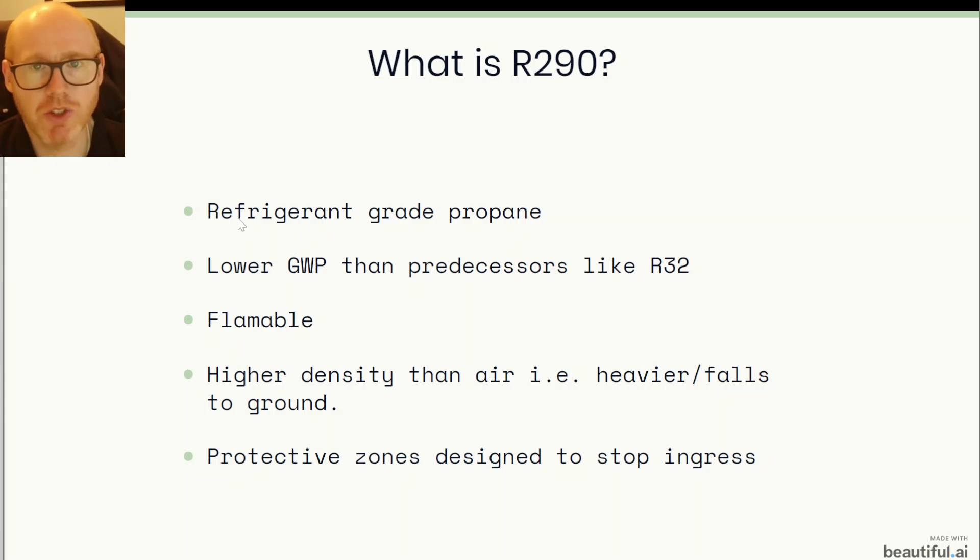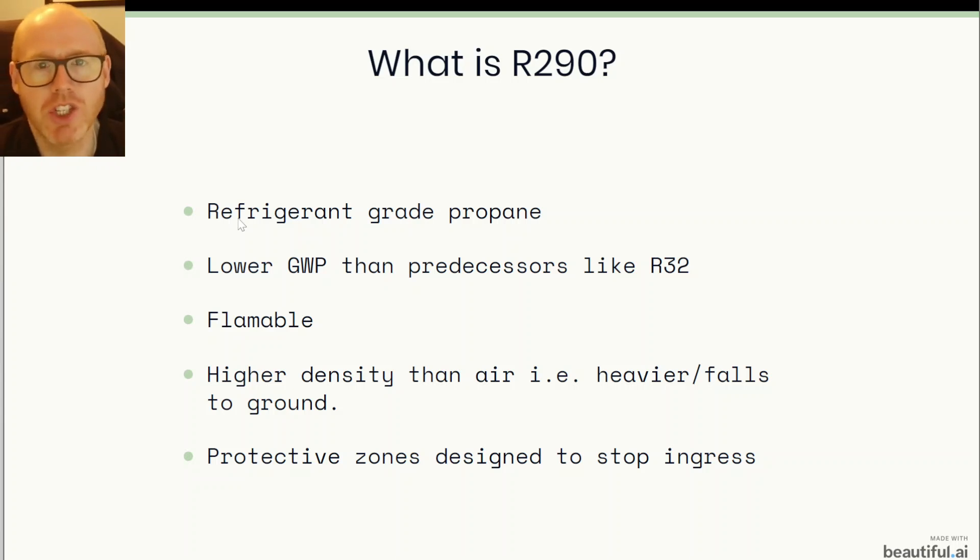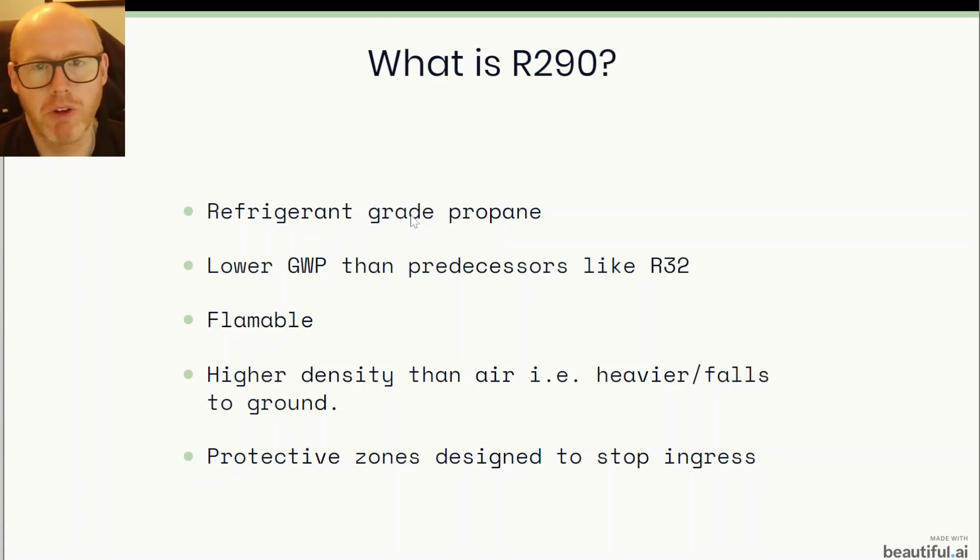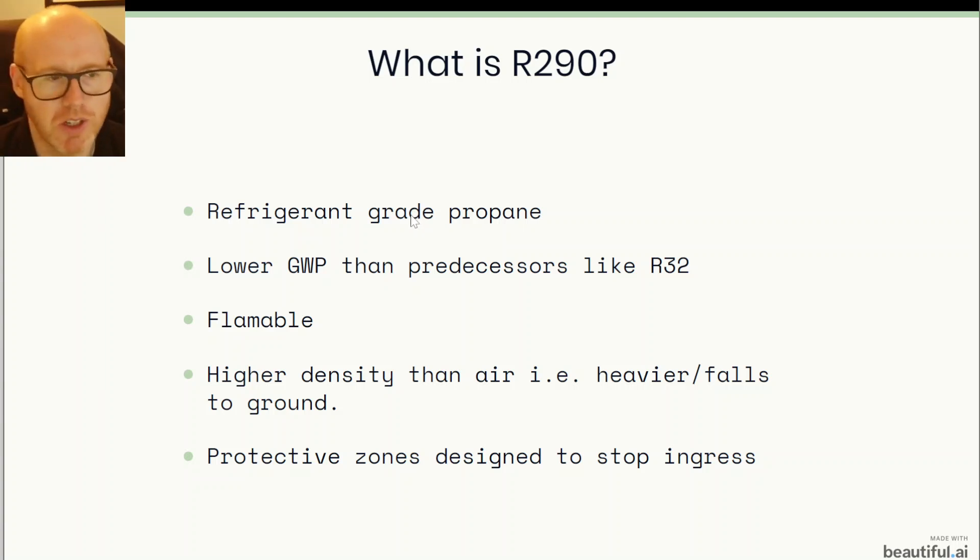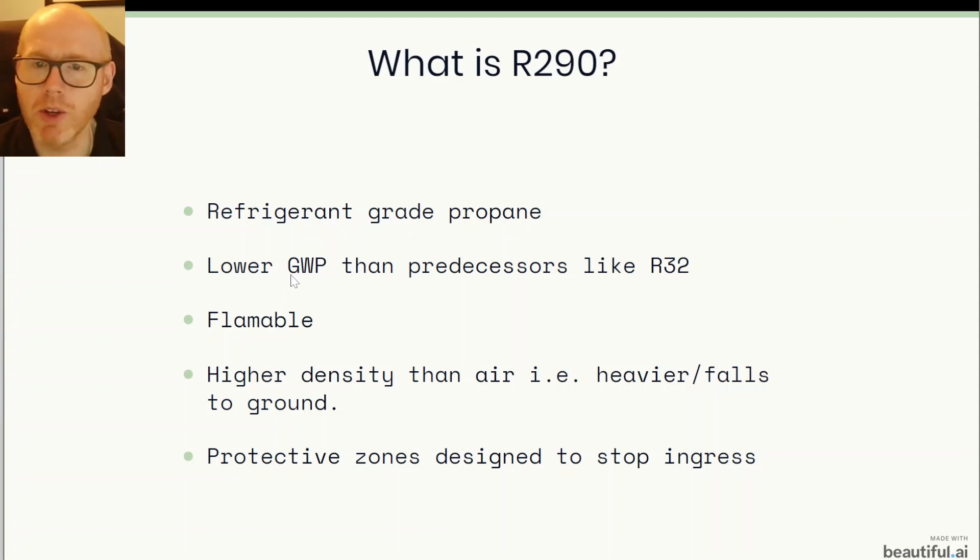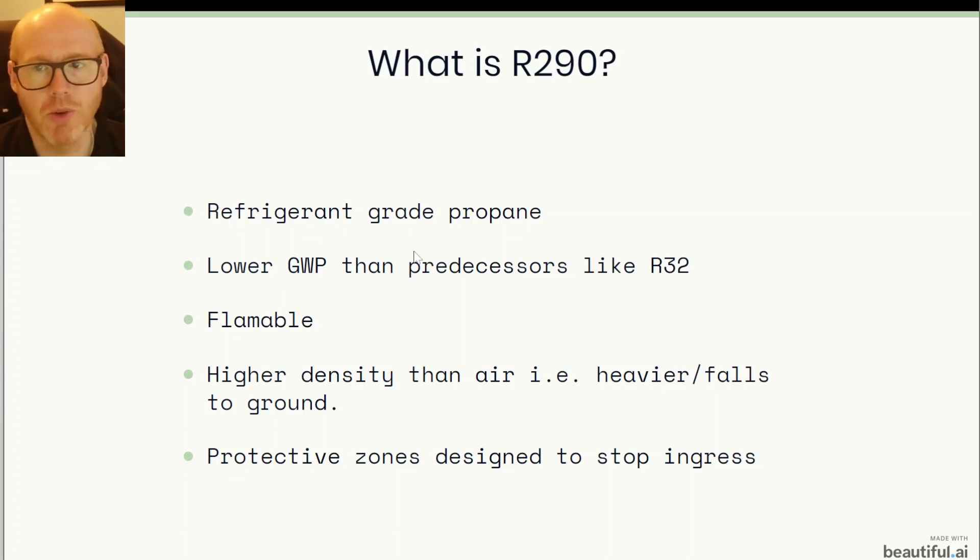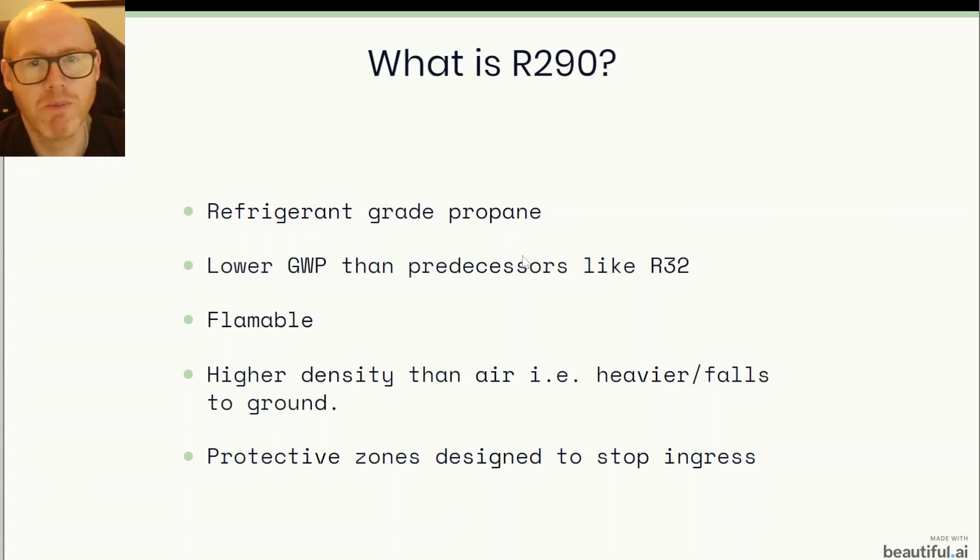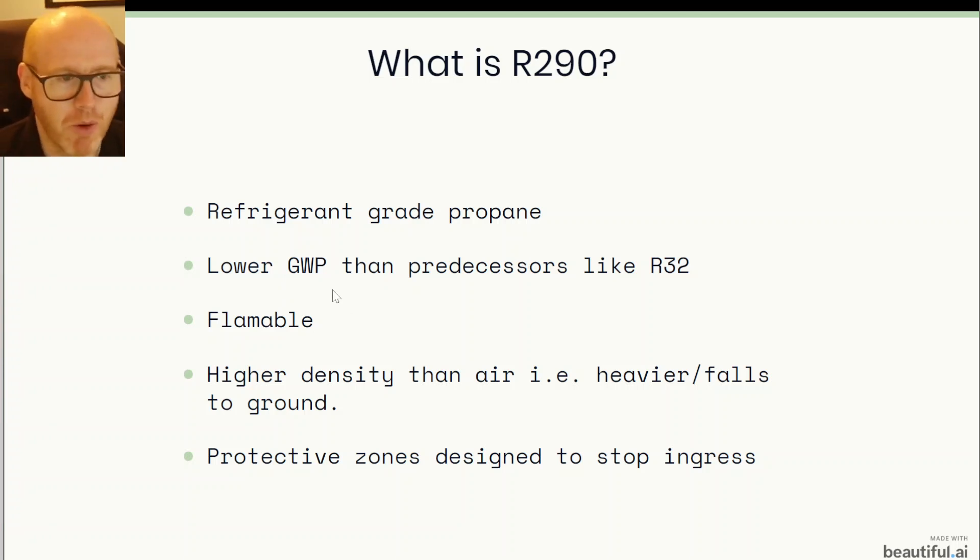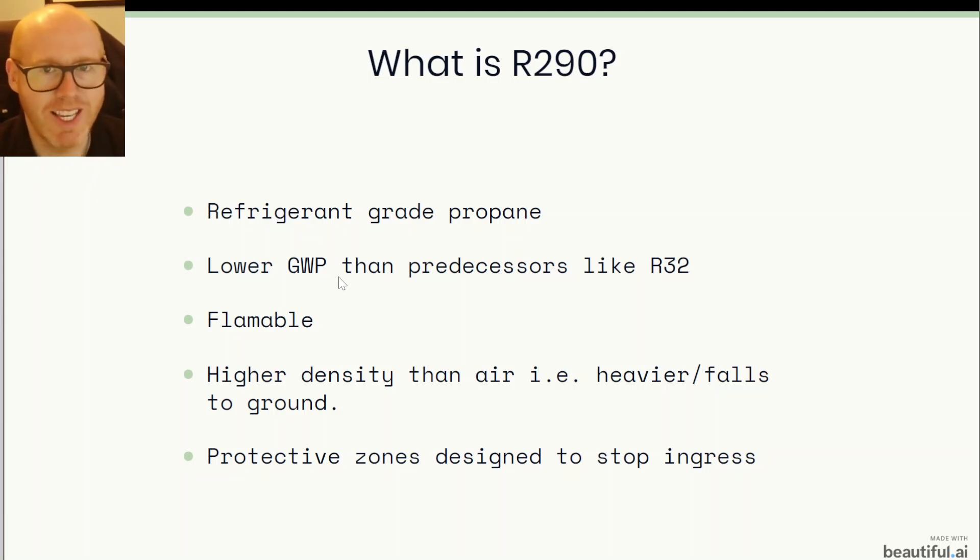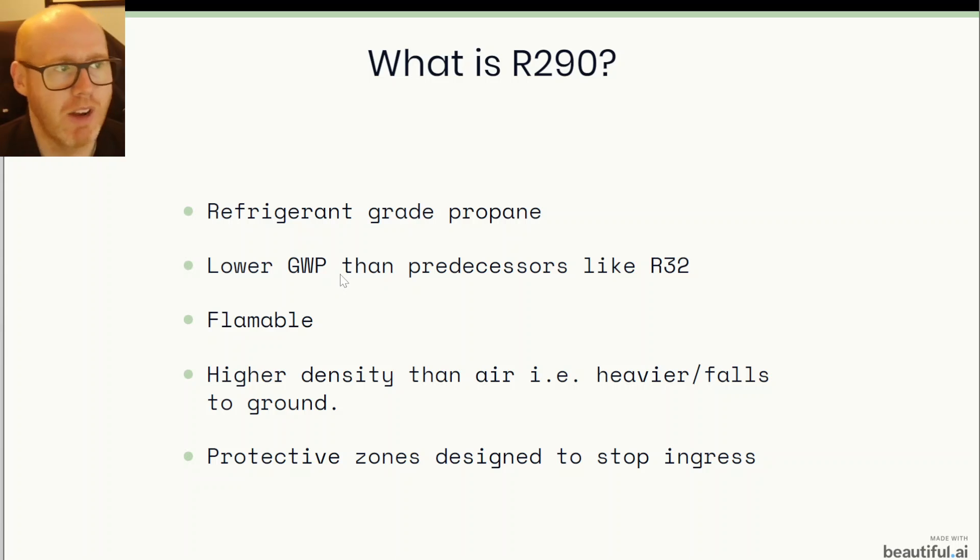It's a refrigerant, it's transferring energy and it is a form of propane but it's a refrigerant grade of propane so it's very very pure to put it in the most basic terms. It has a lower GWP which is global warming potential than the predecessors like R32 and much worse ones that came before that. So if anything does leak out into the environment, the atmosphere, R290 isn't very harmful to our surroundings at all.